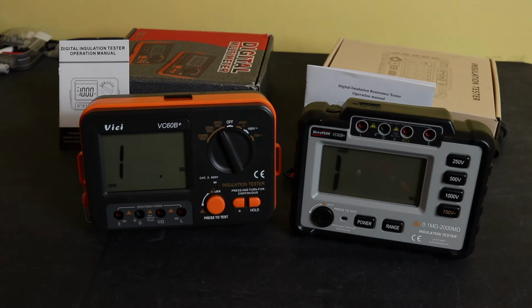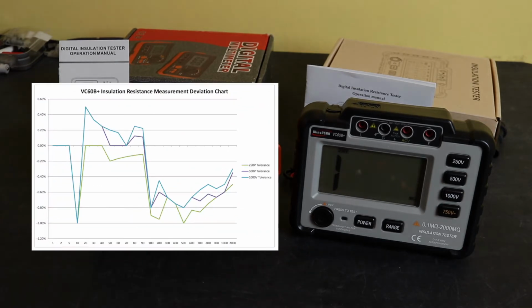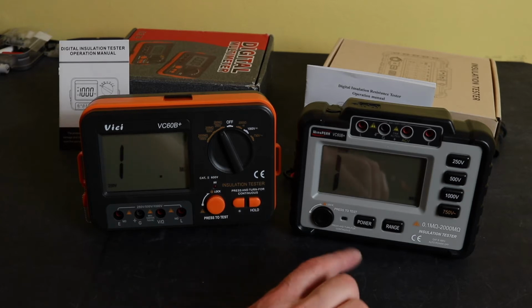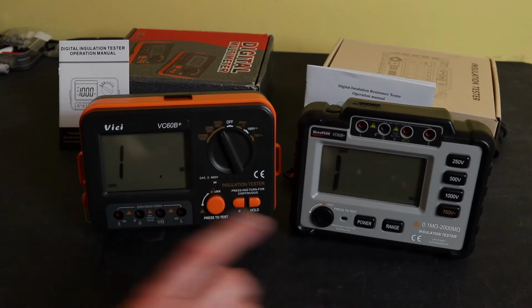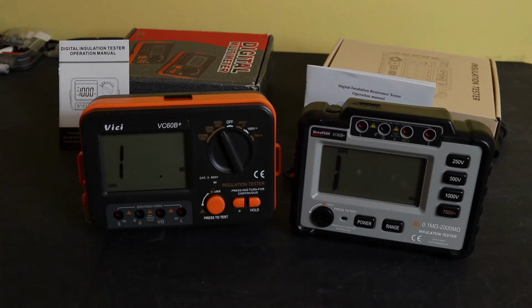Insulation testers aren't the most accurate anyway. It goes up to about 1.8% average accuracy against the WinsPEAK unit that's much more stable. That's got 1.56% accuracy. That's over 77 tests because of the extended range at the lower test voltages on WinsPEAK. So we have 59 tests on the Vici unit there.